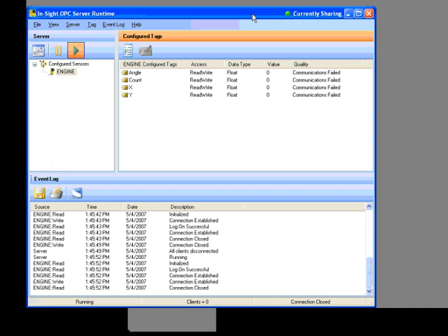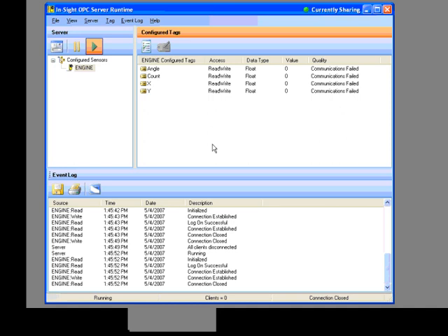I guess what would be the connection then to a given HMI? In the HMI, it would be something similar to what I showed with the Visual Basic code. There'd just be a function that connects to the OPC server, and then a function call to go and read the data using the tag names. So the HMI doesn't need to know where the data is. It's just saying to the server, hey, I have this tag name, I want the data, or I want to write this data. So the HMI programmer doesn't have to know anything about InSight, how it's programmed, or anything. He just has a tag name that has the data. Cool.